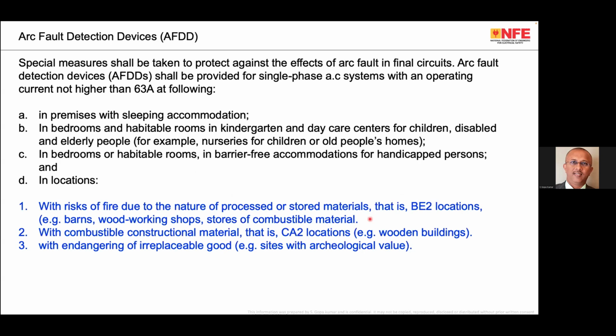Now, with respect to AFDD, the NEC is recommending as below: in premises with sleeping accommodation, in bedrooms and habitable rooms, in kindergarten and daycare centers for children, disabled and elderly people, in bedrooms or habitable rooms, in barrier-free accommodation for handicapped persons, and in locations 1, 2, 3 with risk due to nature of processed materials, nature of stored material. Now, please note that in NEC, up to 63 amps is mentioned, but practically no companies are making 63 amps AFDD. This is what I learned from the market.